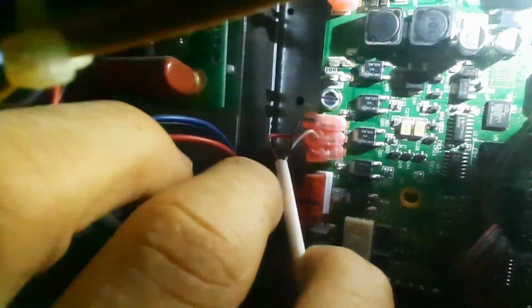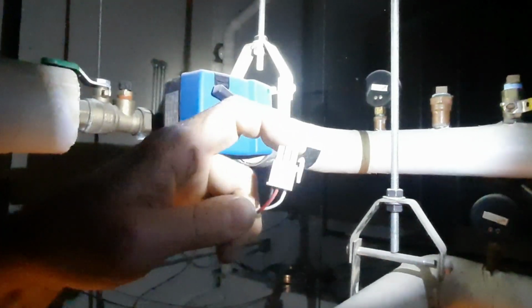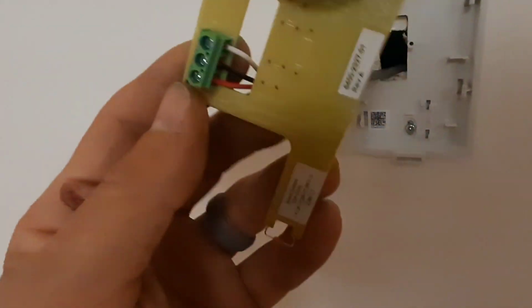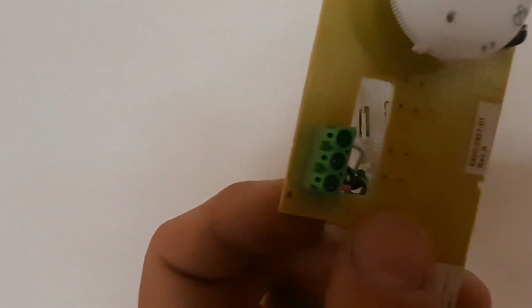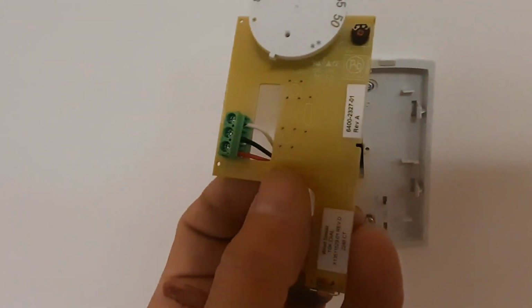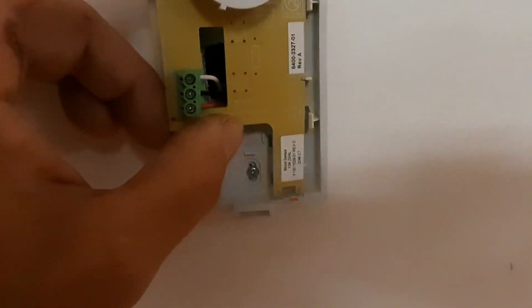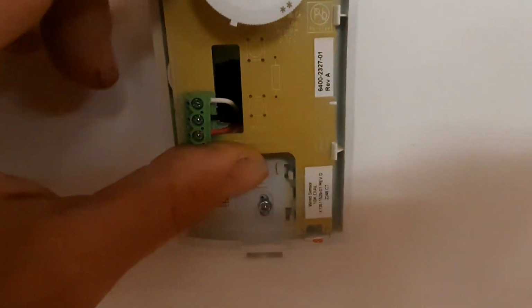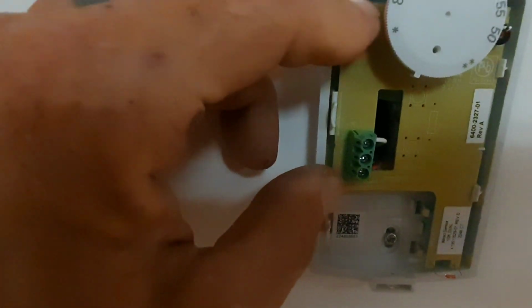And actually I do have wire right there. I know I looked at that, I just don't have the plug. So that white wire is going to go here, and that's going to control my actuator. So I'm probably just going to have to pull that plug and wire nut them together. So we've got our zone, ground, and set, red, black, and white, and this guy is going to pop right back in here. Match up your little clip there in the center behind those, and that's going to snap it in place.